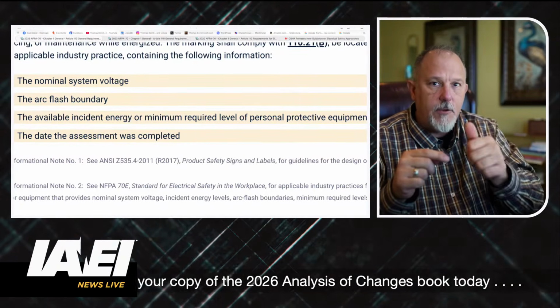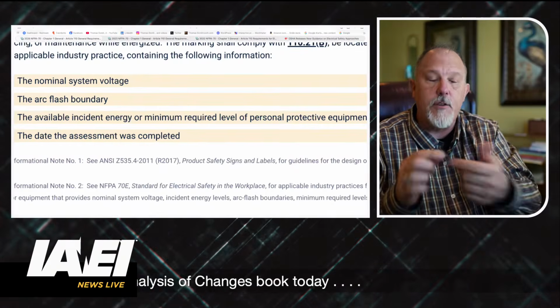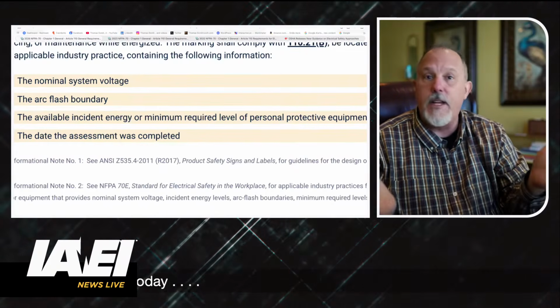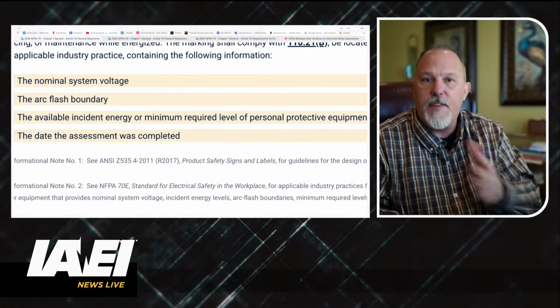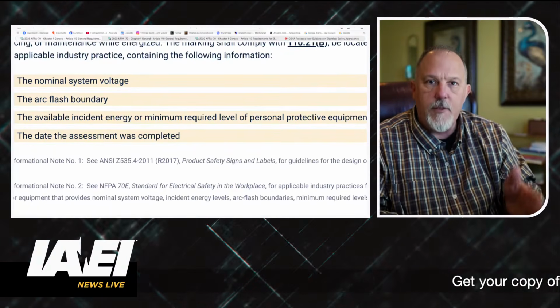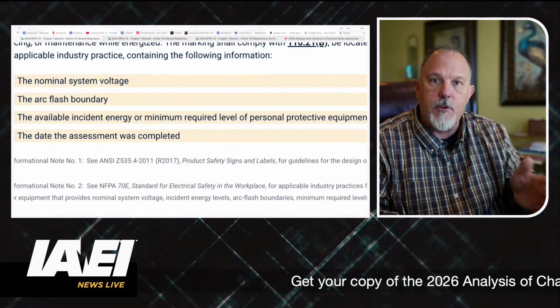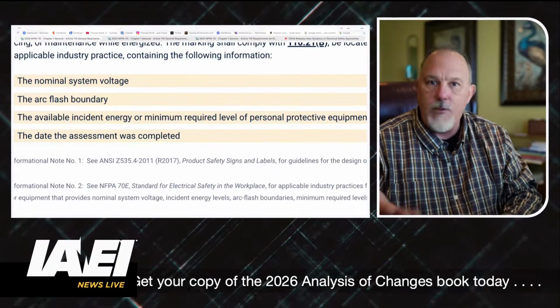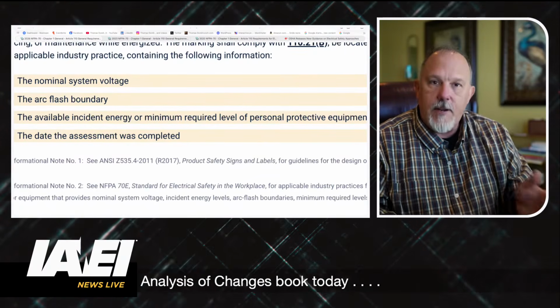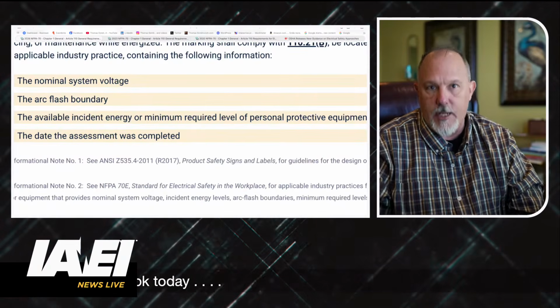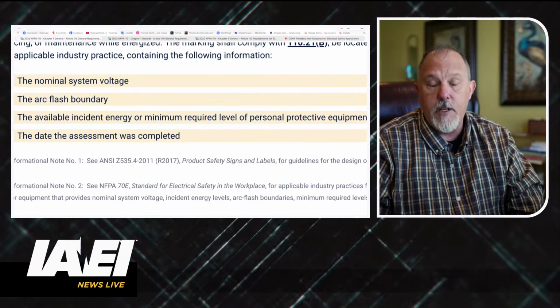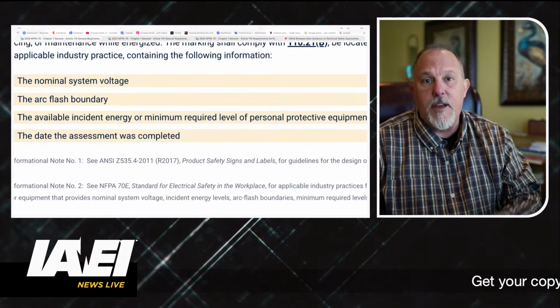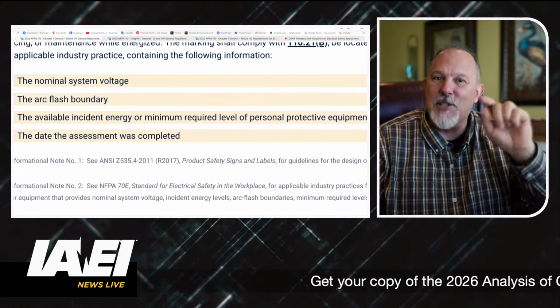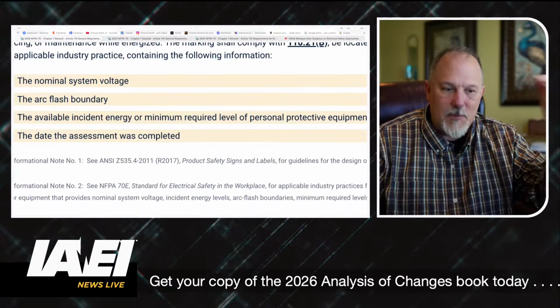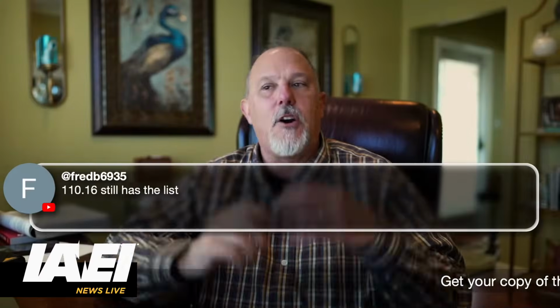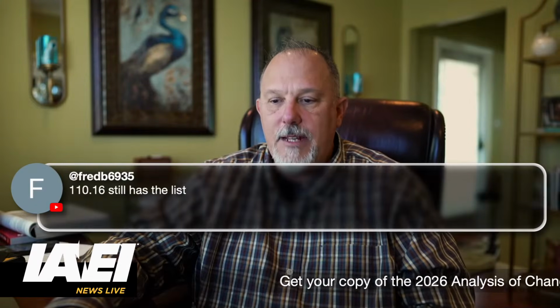One of the criteria is the voltage. Another criteria is the available fault current. So say it's a 480 volt panel board: if that panel board has more than 25,000 amps available fault current at the panel board, you can't use that method. If it's greater than that, then you have to use the calculation method. Capiche? And the calculation method gets more complicated the further from the service that you get.